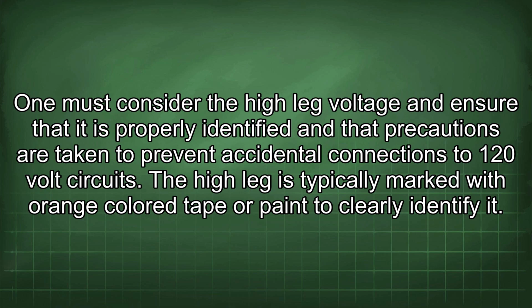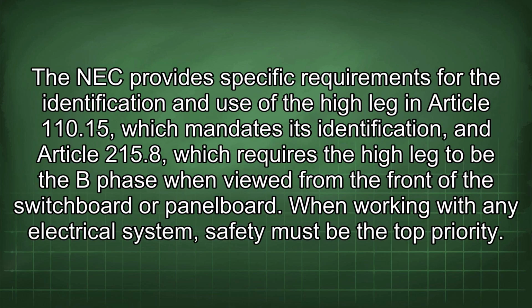One must consider the high leg voltage and ensure that it is properly identified and that precautions are taken to prevent accidental connections to 120 volt circuits. The high leg is typically marked with orange-colored tape or paint to clearly identify it. The NEC provides specific requirements for the identification and use of the high leg in Article 110.15, which mandates its identification, and Article 215.8, which requires the high leg to be the B phase when viewed from the front of the switchboard or panel board.